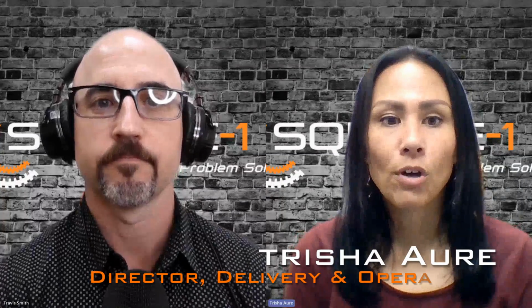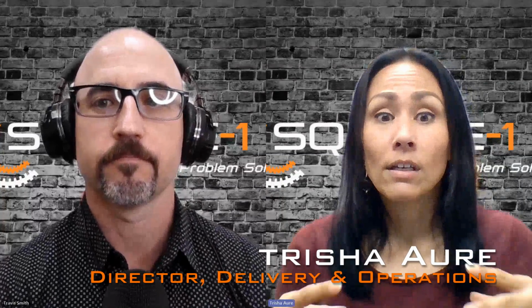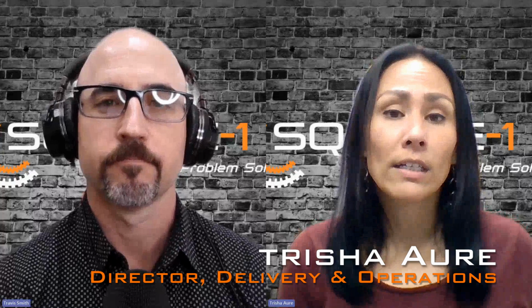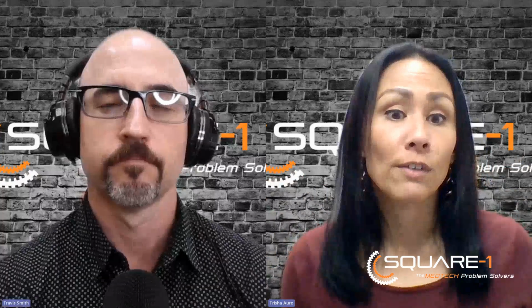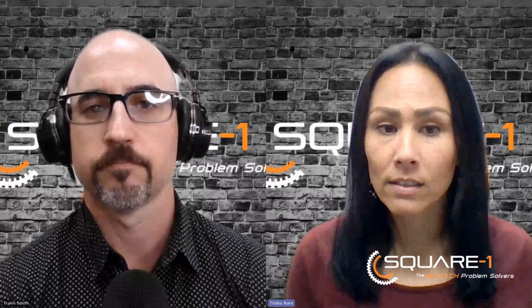Absolutely. And that's a great question. So one of the biggest differences that comes to light as you're looking through the article is, 21 CFR 820 is a US based standard for US regulations, whereas bringing in ISO 13485, it's an international standard that opened doors for global markets while looking at the entire life cycle of the device.